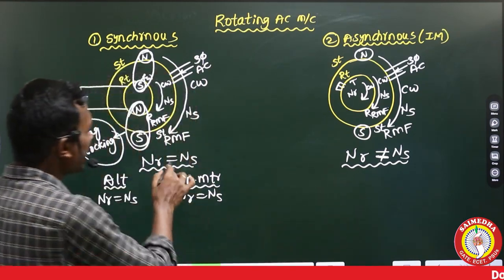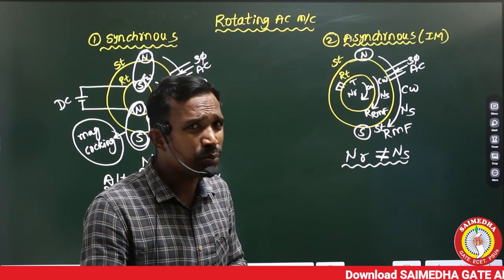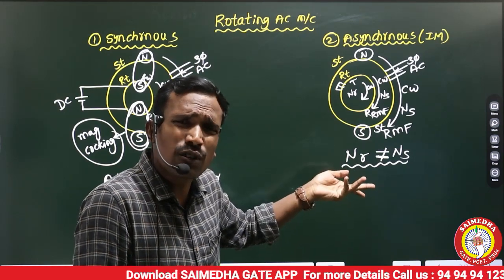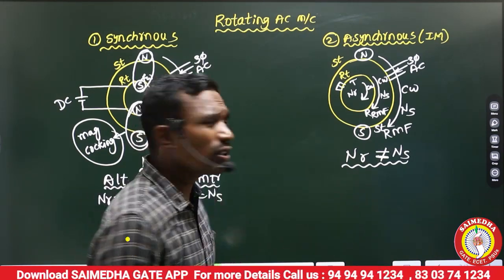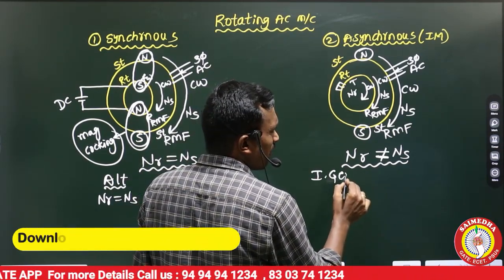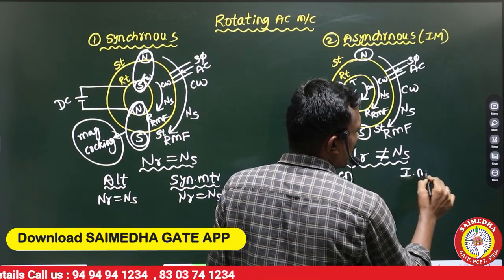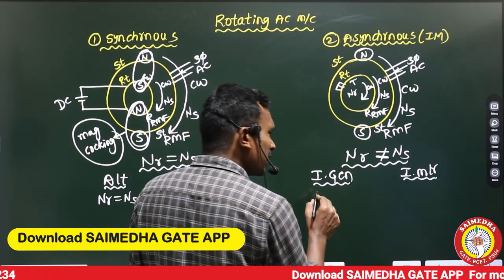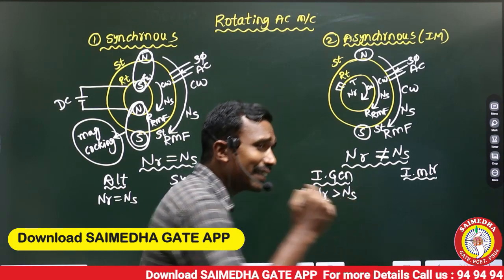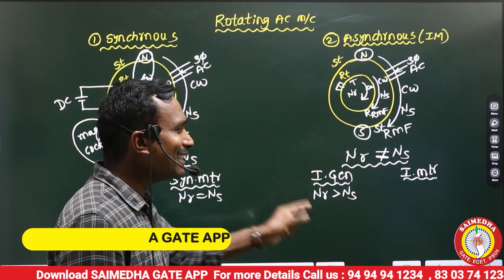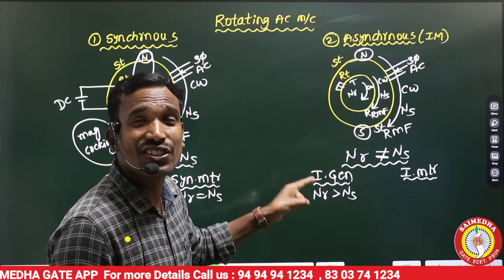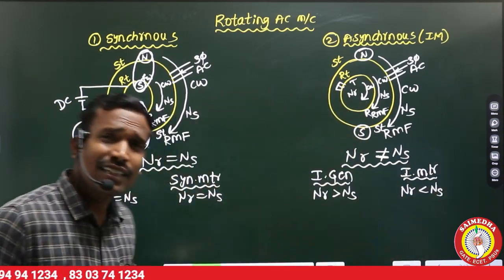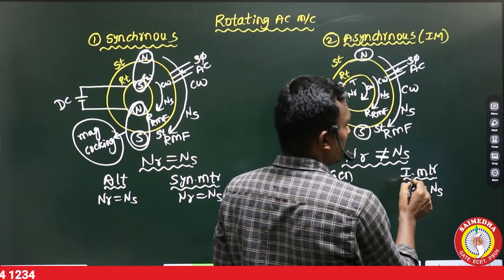Not equal means either less or more — we have two modes of operation. One is called induction generator and the other is called induction motor. In the induction generator, the rotor speed is greater than the synchronous speed. In the induction motor, the rotor speed is less than the synchronous speed. These are the main differences.